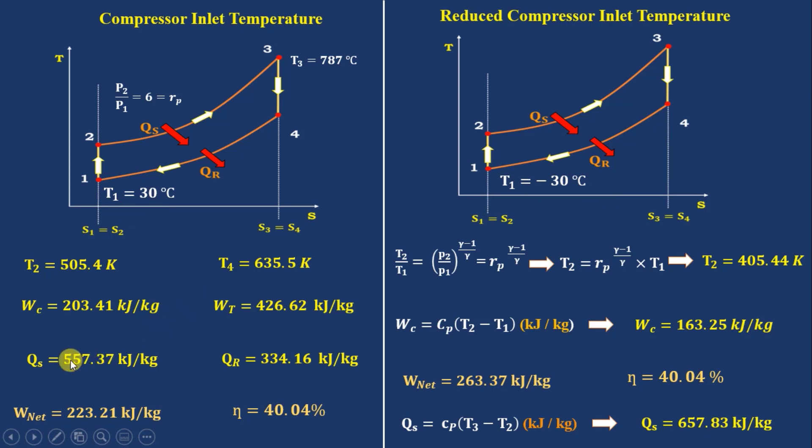Whereas for 30 degrees Celsius, it is 557.37 kJ per kg. Here you can check it: 100 kJ per kg is increased. This means when inlet temperature of compressor reduces automatically, the heat given to the combustion chamber will increase.